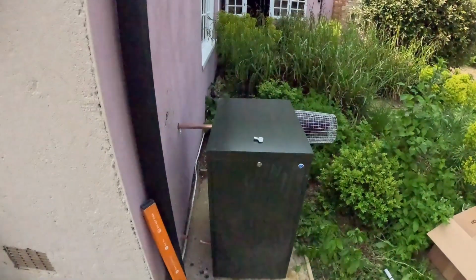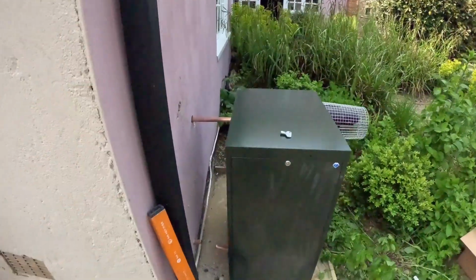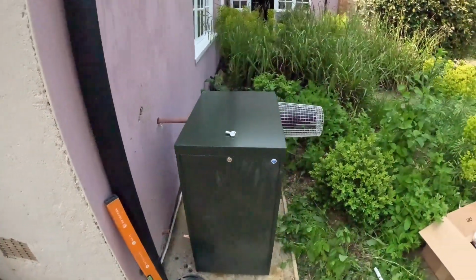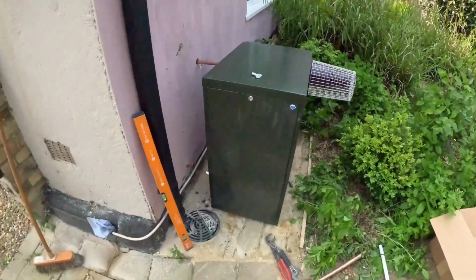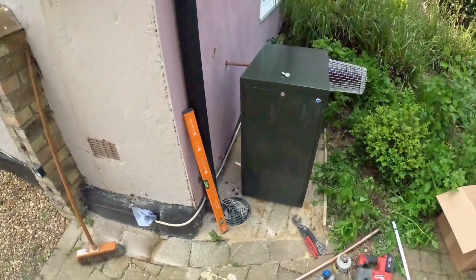So that's day one pretty much done now, we're just having a good tidy up. As you can see, we've got one of the pipes through at the top, the second one needs to be plumbed up tomorrow. The flue's all in, I'll get the condense done tomorrow, and all the internal pipe work tomorrow. So I've got the plate heat exchanger left to do, dirt separator, air separator, pump, connect it to the old system as well, obviously, and then a bit of wiring.